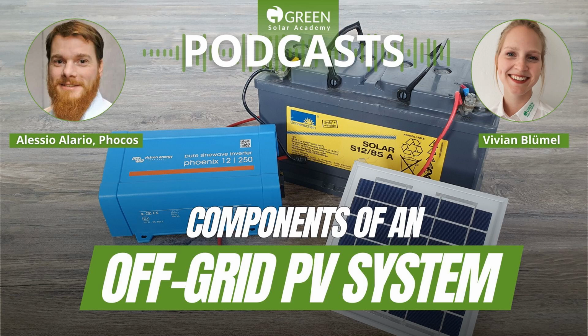But if you have just 2-3 loads to power, and if you're talking about less than 1 kilowatt, then it tends to be quite practical to have an electrical outlet. Also, there's a big difference sometimes in quality, but also certainly in the amount of settings you have. For these smaller inverters, you tend to have maybe just one setting, which would be 50 or 60 hertz. Sometimes you can influence how low the inverter is allowed to discharge the battery before disconnecting, remembering the low voltage disconnect functionality of charge controllers, and the same for inverters. But essentially that's pretty much all you can do in terms of settings for the small inverters.